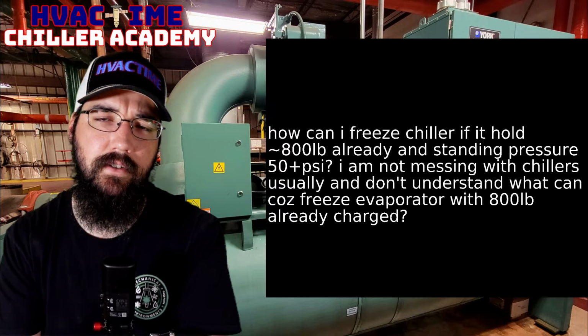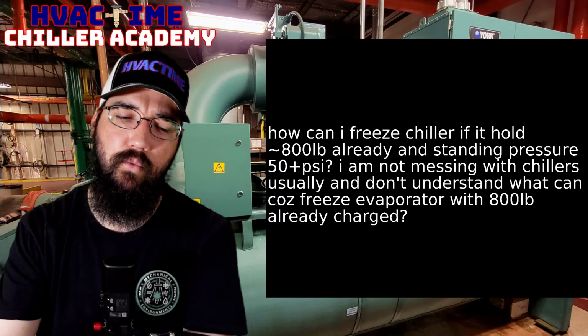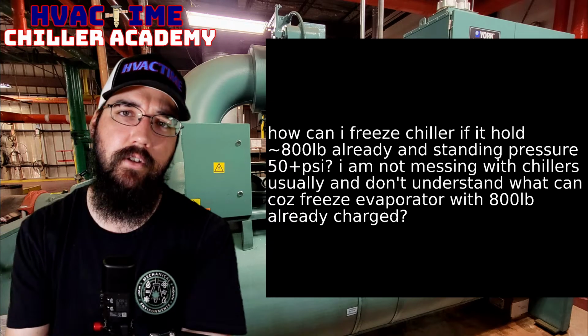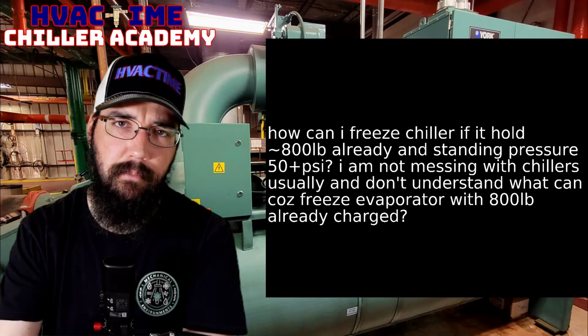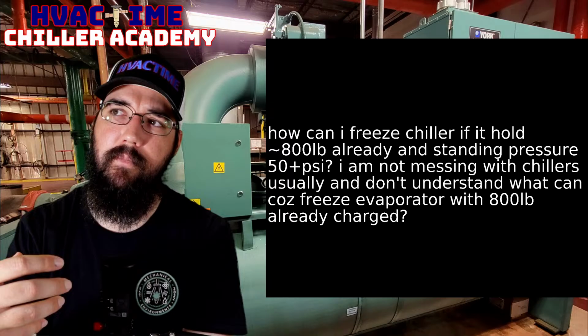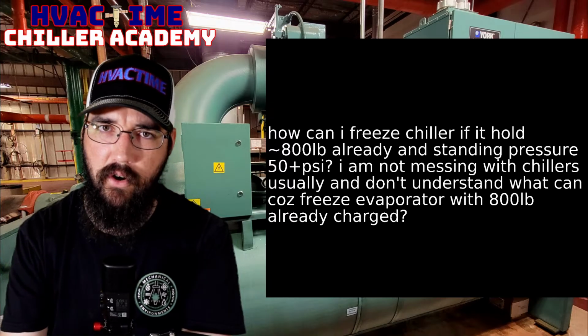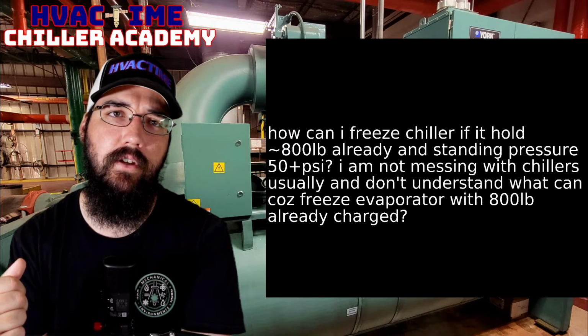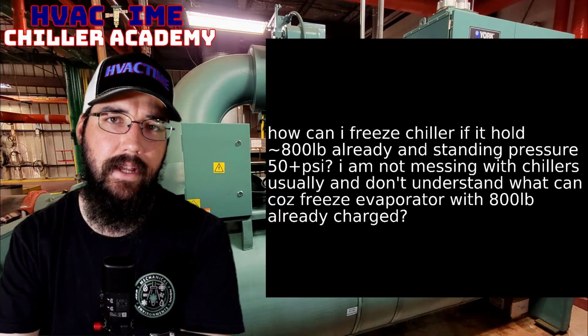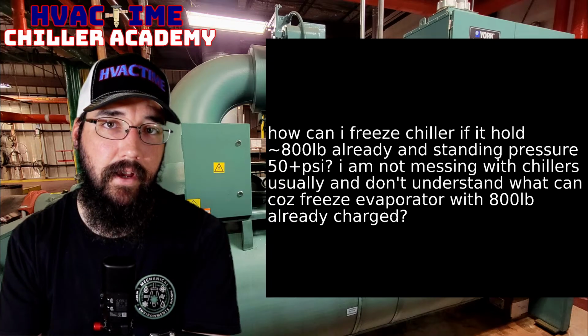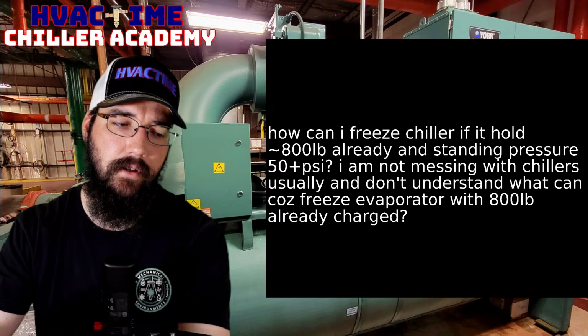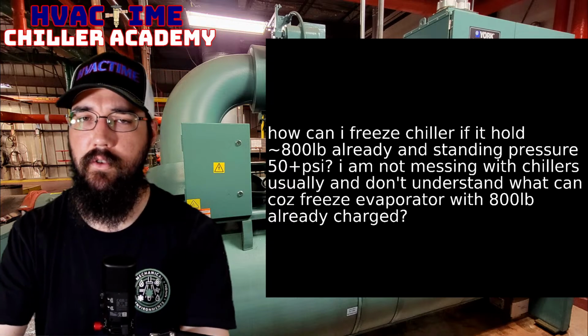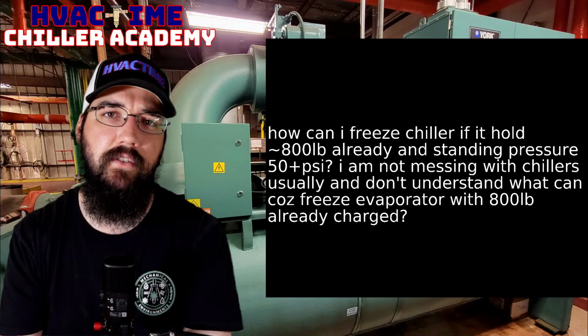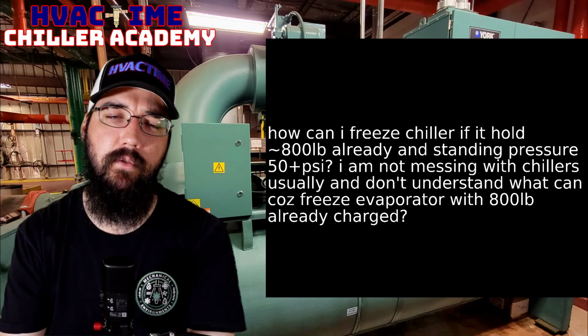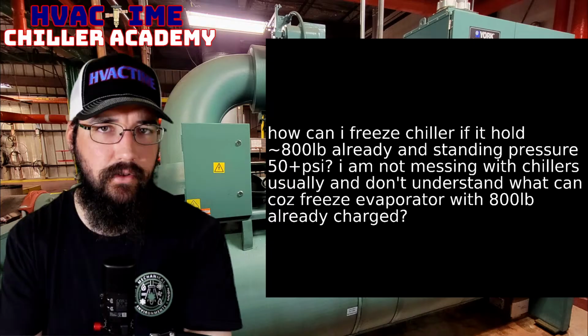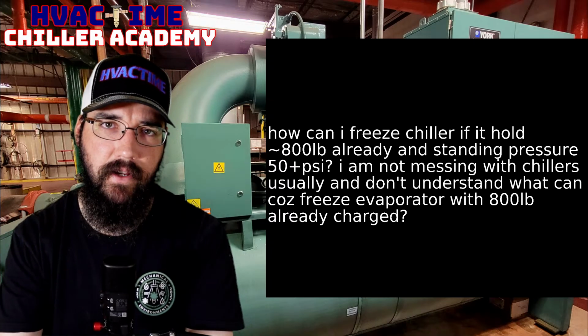I've talked about this a lot recently. If you pre-charge vapor into the chiller and get that pressure up, charging liquid from there is far less of a risk versus sending straight liquid in right out of the gate after your evacuation, which can cause liquid refrigerant to make contact with the water. If you're flowing water, there are still ways of mitigating that risk. Flowing water is one of them, and either way you go, it's still recommended to flow water, whether you pre-charge vapor or not.